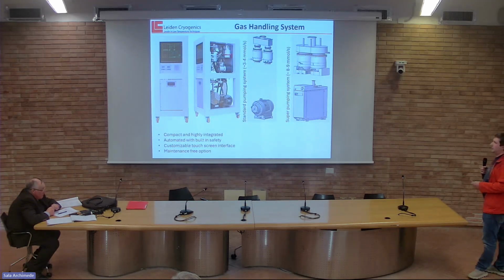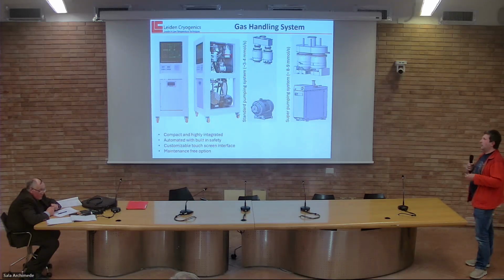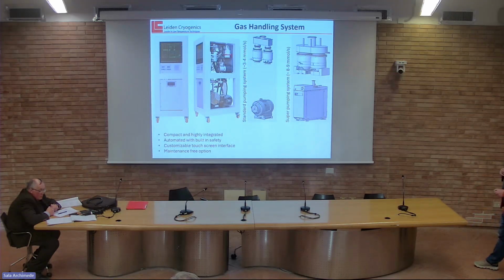Our gas handlings are very compact and very integrated. So the mixture is stored inside the frame of the gas handling system. So there is no separate mixture tank that takes space, and it's very compact. It also has a microprocessor inside, so it doesn't require any laptop or external connection to operate. From 4 Kelvin down, you can just press a start button, and the system will cool to base temperature and will stay at base temperature.